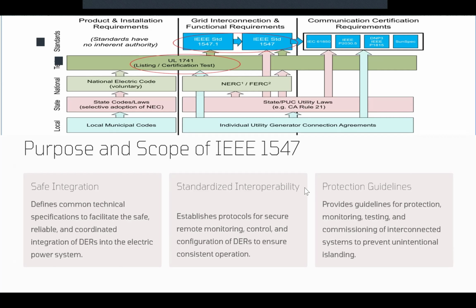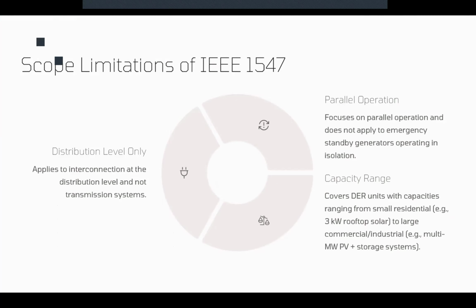Now, these are the purposes, but what are the scope and limitations of the scope for this standard? As you know, every standard has its scope, so it applies to certain categories of equipment or systems. It's not a general set of rules for everything. Okay. Now, what are the systems? The first aspect that limits the scope of IEEE 1547 is that it applies exclusively to interconnection at the distribution level. So when we talk about a transmission level system or the bulk power grid, this standard does not cover those levels. Okay.